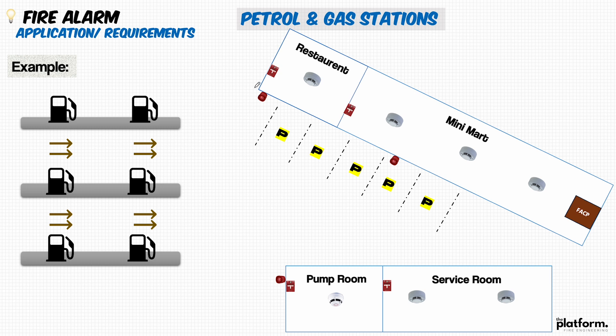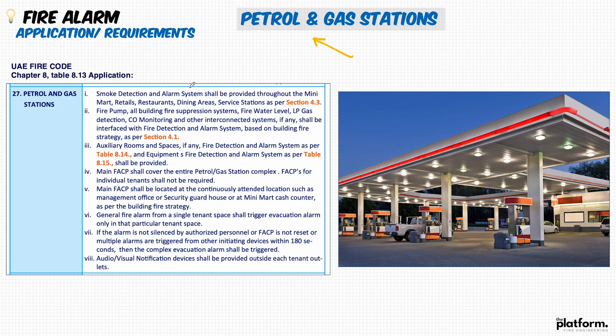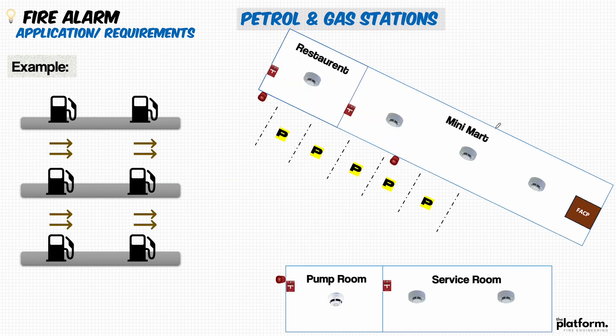I have drafted a quick layout to illustrate where we provide the fire alarm system. Point number one: fire alarm shall be provided throughout the mini market, retail areas, restaurant and dining areas, and service stations. So if we have a mini mart, a restaurant, auxiliary rooms, or any enclosed service rooms, we need to add smoke detection and the fire alarm. Smoke detectors are provided here, and the distances between devices follow the UAE Fire Life Safety Code of Practice.